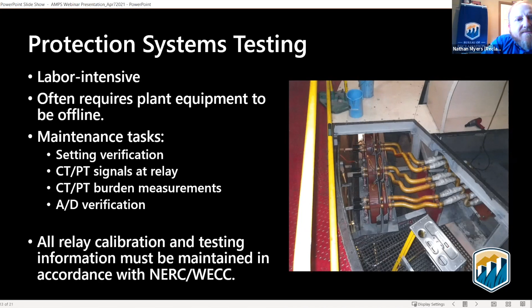As we look at the overall physical locations of our protection systems, the instrument transformers are typically located at or near the equipment that we're trying to protect, for example, the generators and transformers. It can be challenging to access these instrument transformers based on the configuration of the equipment. Oftentimes, the instrument transformers might be located in an area that's protected by carbon dioxide, for example, for fire suppression, and we'd have to put in several safety factors to ensure that if the CO2 was released, we would not be asphyxiated. In other instances, the instrument transformers might be buried deep within switchgear, requiring the removal of several panels to be able to get to them.